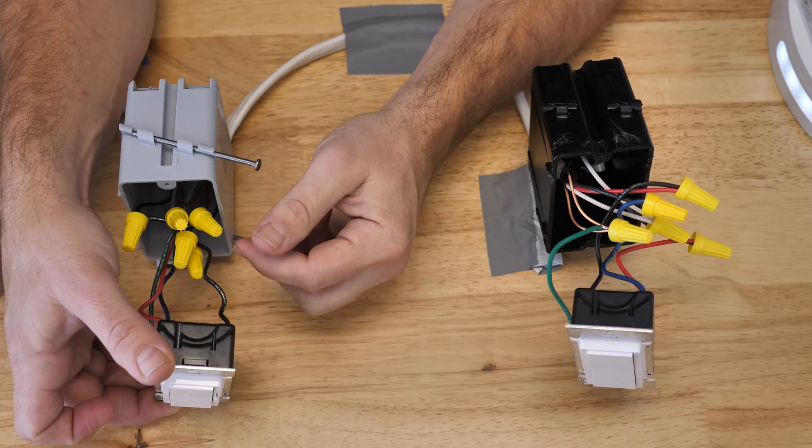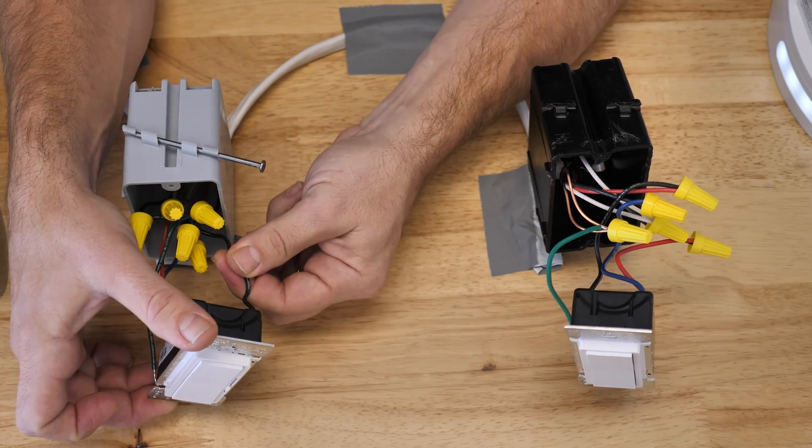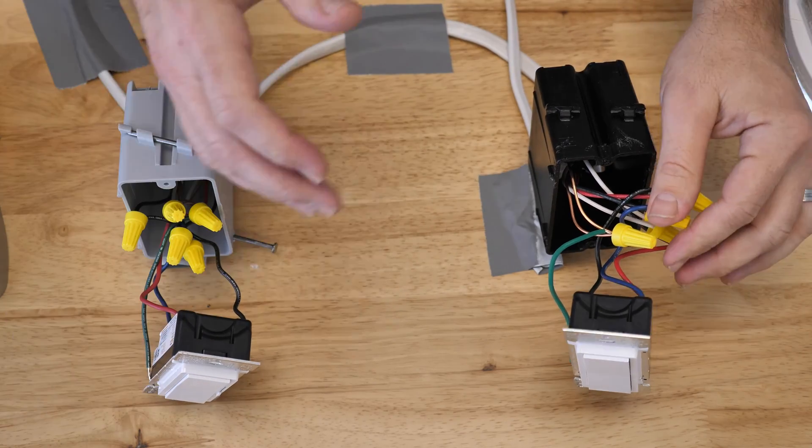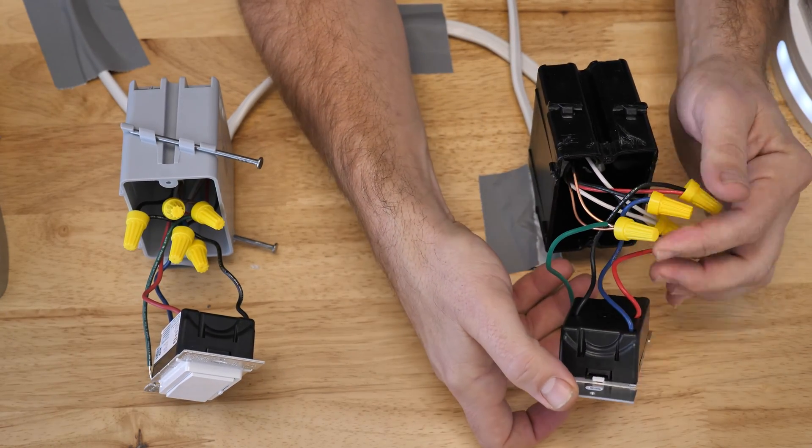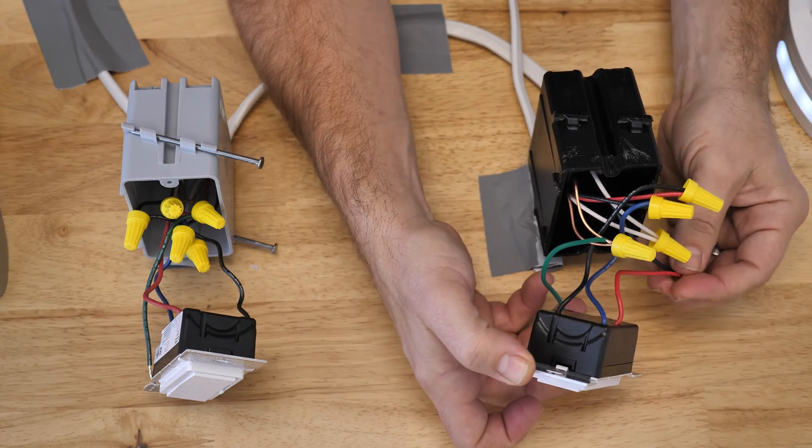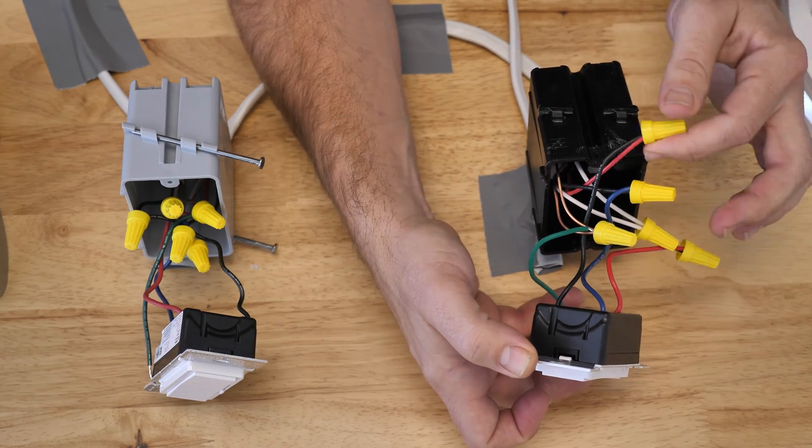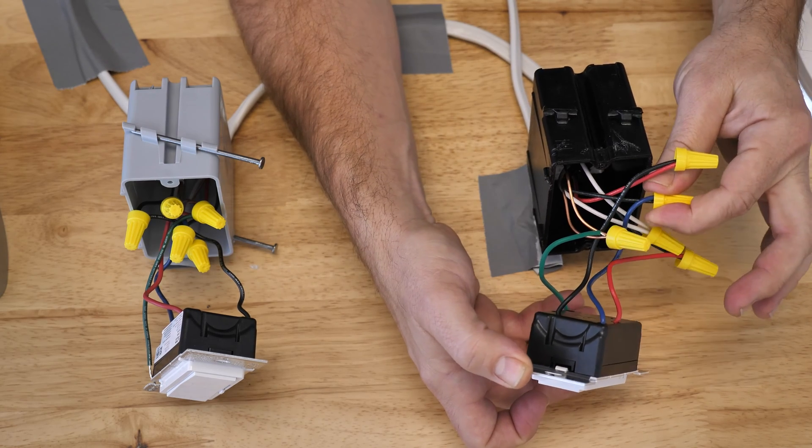To use it as a three-way, you're going to notice that we use our black as our power coming in, and our red and our blue become our travelers to our other switching location, which we will just match on the other side. In this particular application, we use black to tie the red, and we used red to tie with the black feed, and then we did a black with the blue.